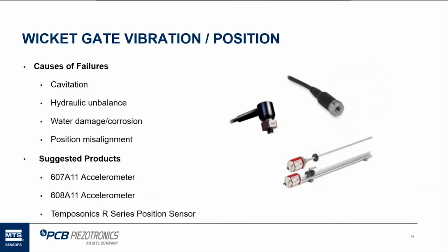Wicket gate vibration, position, cavitation, of course, causes wicket gate vibration along with hydraulic problems, damage from water and corrosion. And the cleanest water and softest water in the world still can damage equipment, especially when it's flowing at a high velocity past this wicket gate all the time. So there's always going to be water damage on a wicket gate.